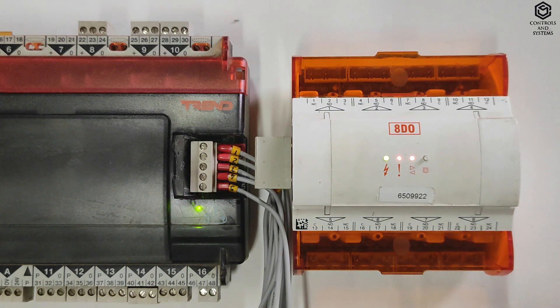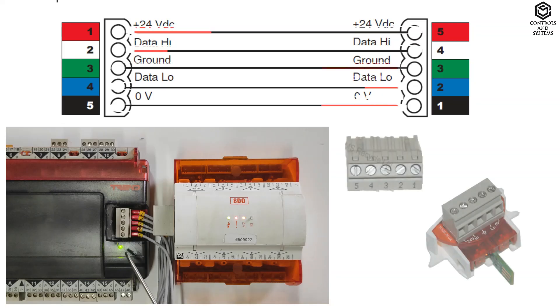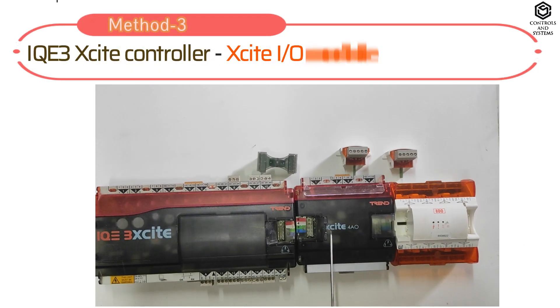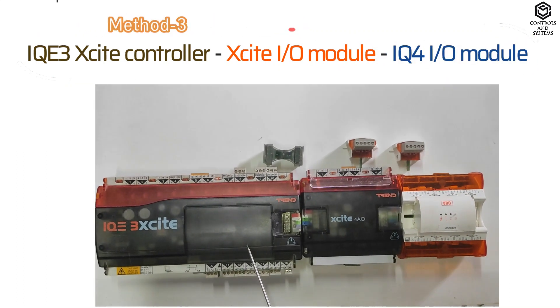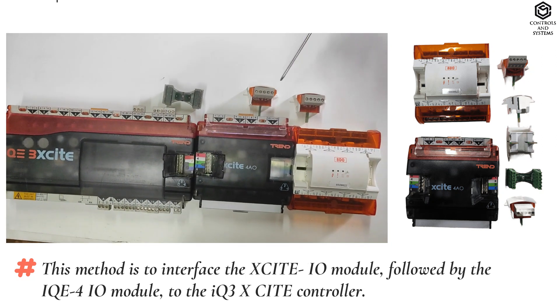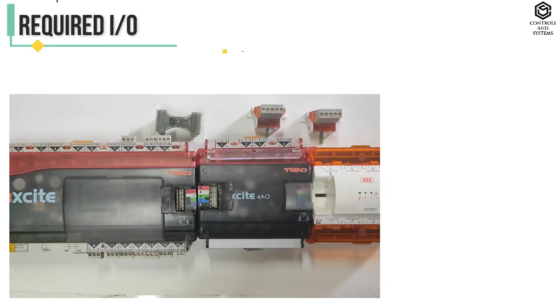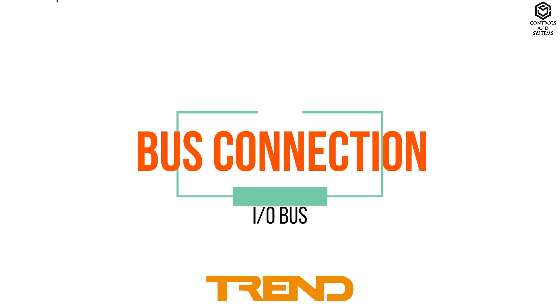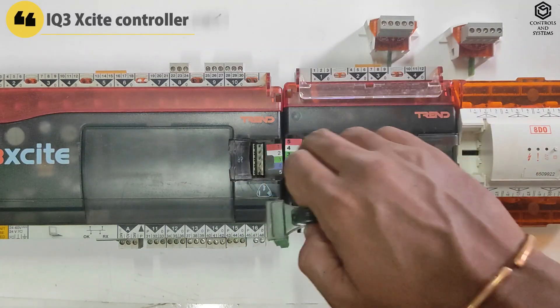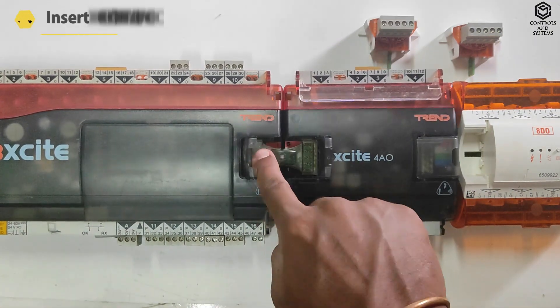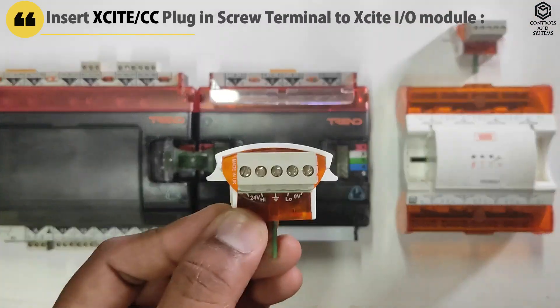Now switch on the IQ3 Xcite controller power supply. This is the I.O. bus connection diagram of the IQ3 Xcite controller to the IQ4 I.O. module. IQ3 Xcite controller to Xcite I.O. module and IQ4 I.O. module: this method interfaces the IQ3 Xcite I.O. module followed by the IQ4 I.O. module to the IQ3 Xcite controller. Required I.O. buses are Xcite IC, IQ4 IC ADPT, and Xcite CC. First, connect the IQ3 Xcite controller and Xcite I.O. module using the short rigid interconnector or jumper module.